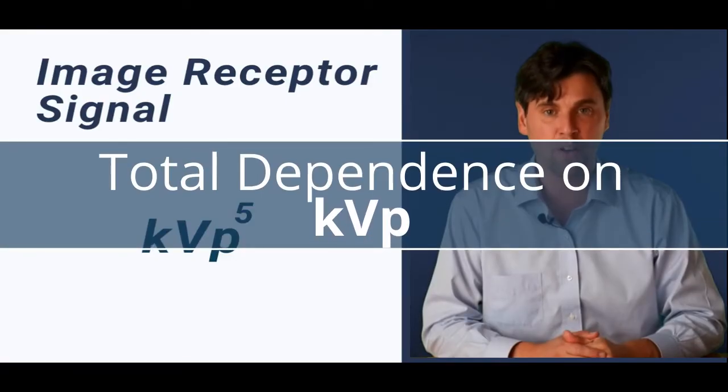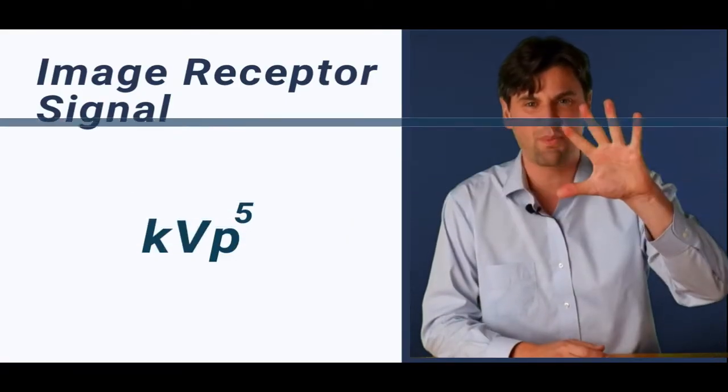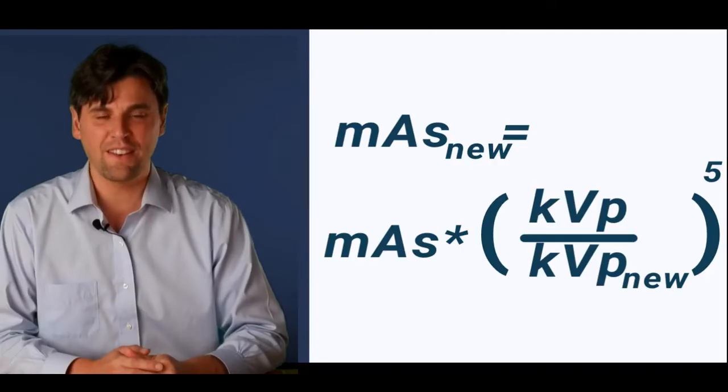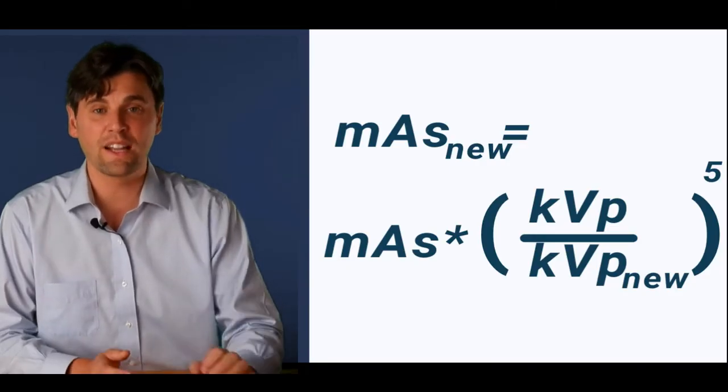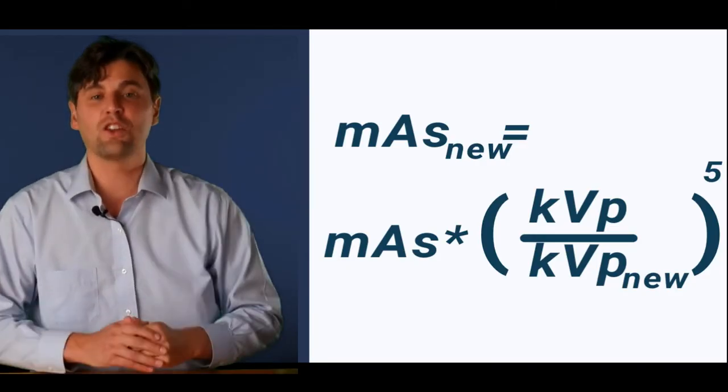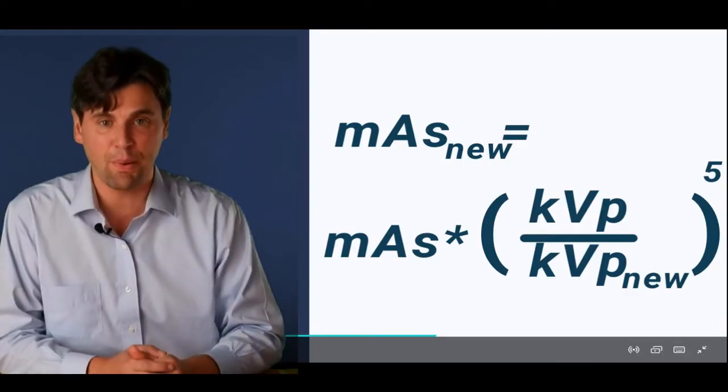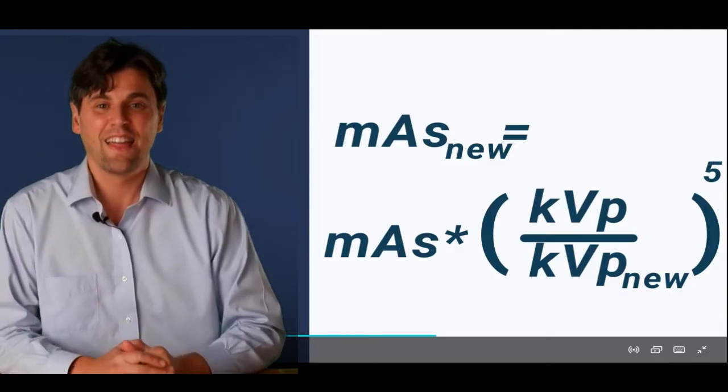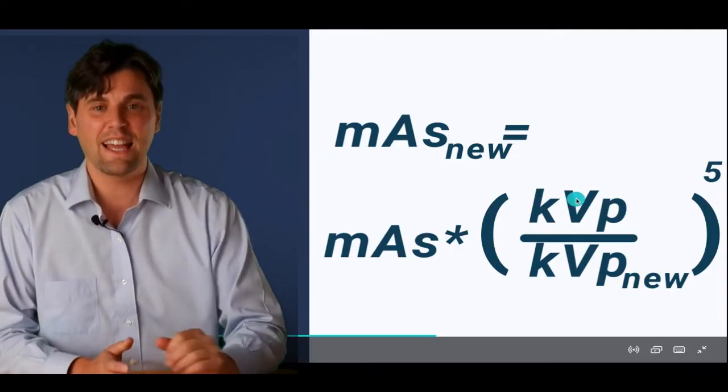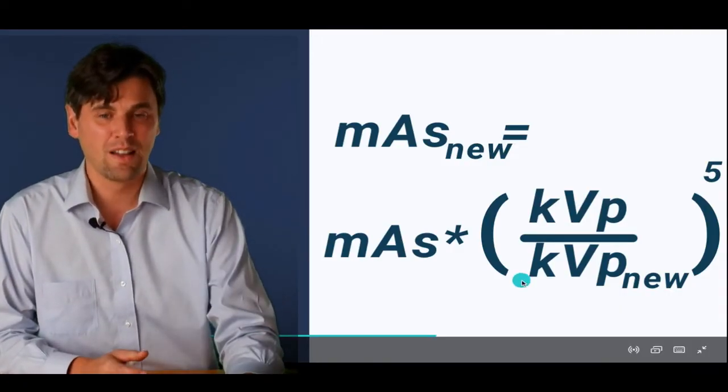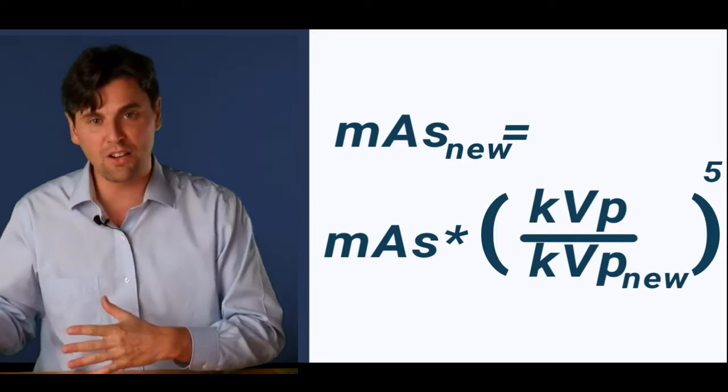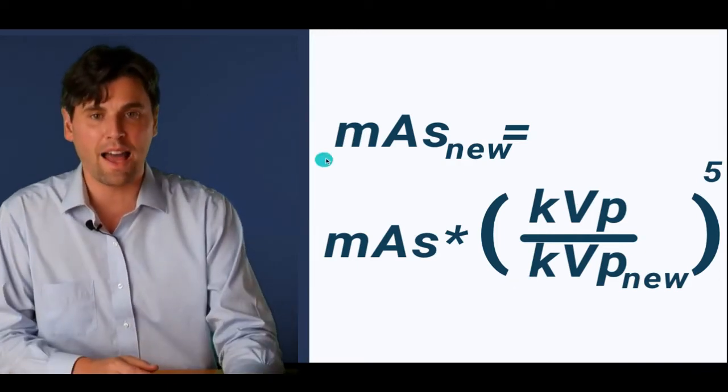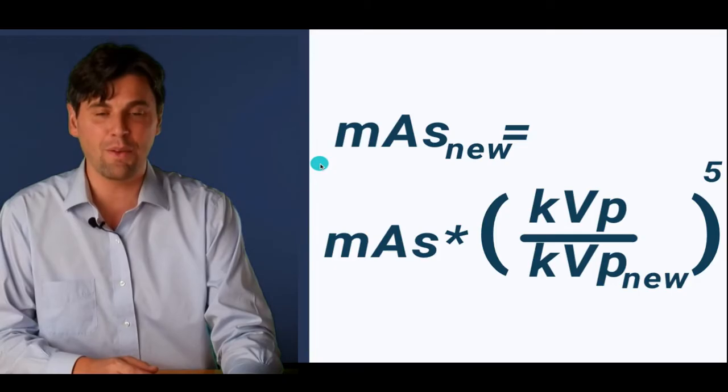Measured at the image receptor goes roughly like KVP to the fifth power then. You're changing your protocol from you have a given MAS in your protocol and then you need to change the KVP from KVP to KVP new. Then you want to calculate the MAS new.